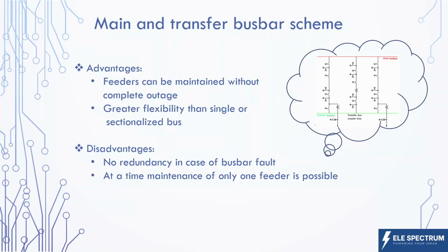So in advantages, the main thing is that feeders can be maintained without a complete outage, as we can maintain the feeder through the transfer bus coupler, and we have greater flexibility than the single or sectionalized bus bar scheme. In terms of disadvantages, we do not have any redundancy in case of a bus bar fault, as all the feeders are connected to only a single bus bar, and we don't have any redundancy for that. Also, if we want to maintain more than one feeder at a time, then it is not possible. This bus bar scheme is generally used up to 145 kV voltage in the transmission system. This scheme gives better flexibility than the single bus bar or sectionalized bus bar scheme with some additional cost.